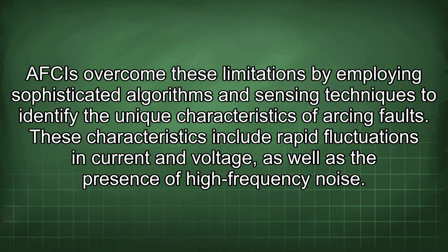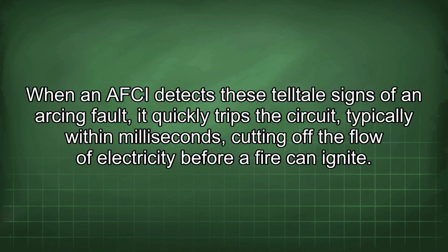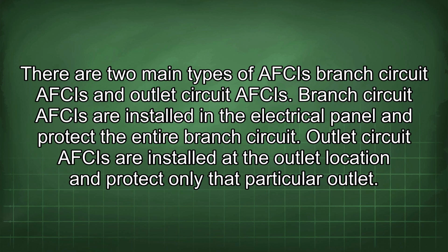AFCIs overcome these limitations by employing sophisticated algorithms and sensing techniques to identify the unique characteristics of arcing faults. These characteristics include rapid fluctuations in current and voltage, as well as the presence of high-frequency noise. When an AFCI detects these telltale signs of an arcing fault, it quickly trips the circuit, typically within milliseconds, cutting off the flow of electricity before a fire can ignite. There are two main types of AFCIs: branch circuit AFCIs and outlet circuit AFCIs. Branch circuit AFCIs are installed in the electrical panel and protect the entire branch circuit. Outlet circuit AFCIs are installed at the outlet location and protect only that particular outlet.